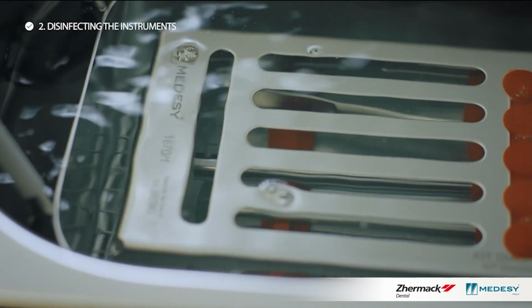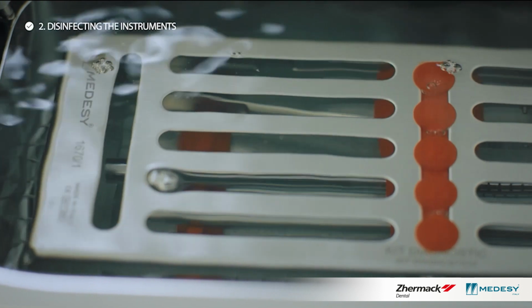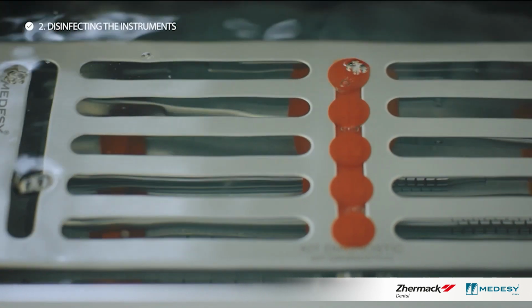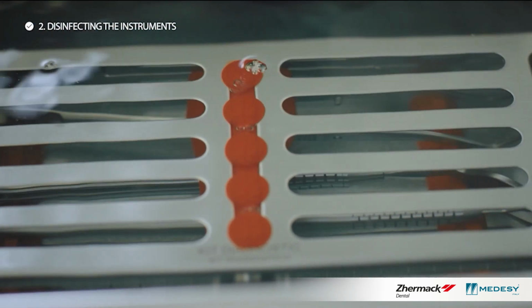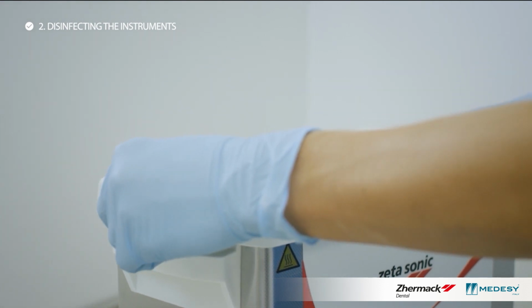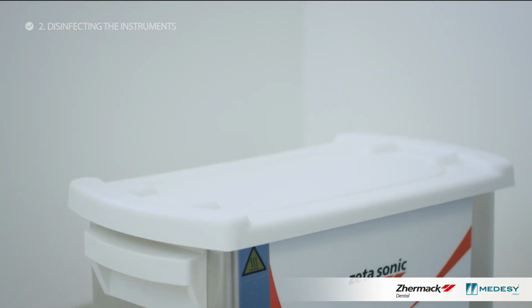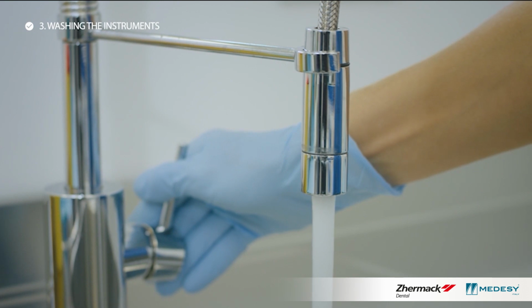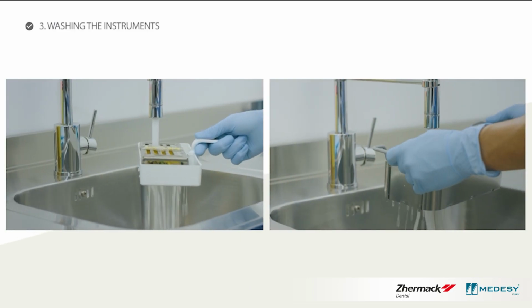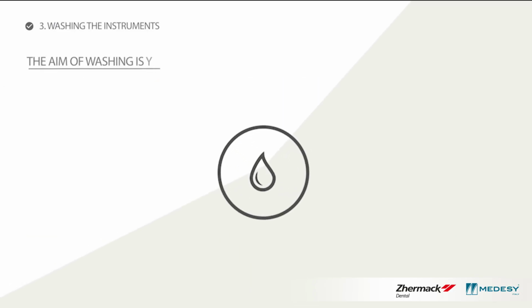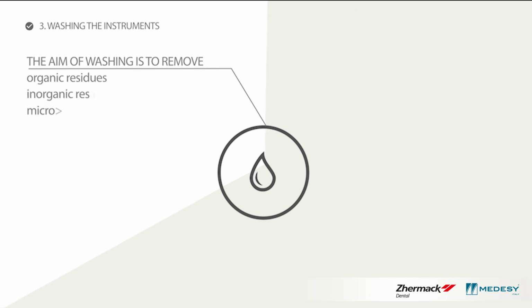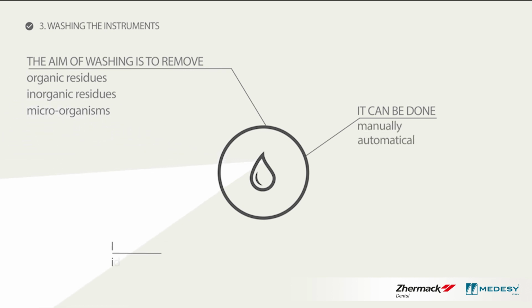Avoid placing aluminum or titanium instruments in the ultrasonic bath, as it could damage the material and color of the instrument. The disinfected material must be rinsed thoroughly before washing. The aim of washing is to remove organic and inorganic residues and microorganisms. This can be done either manually or automatically in an instrument washer or thermal disinfector.